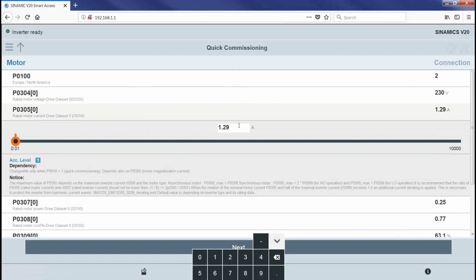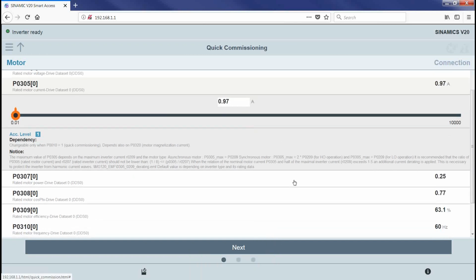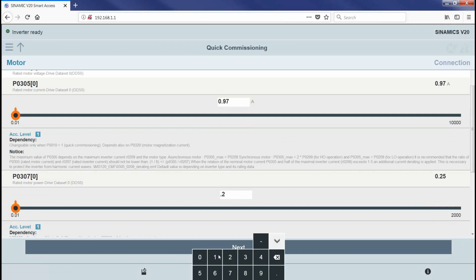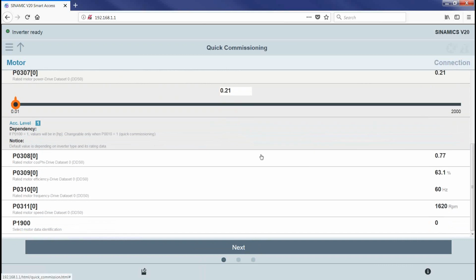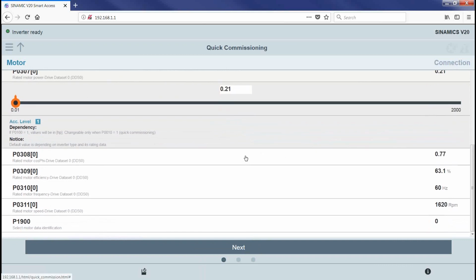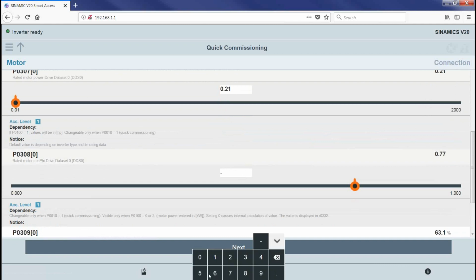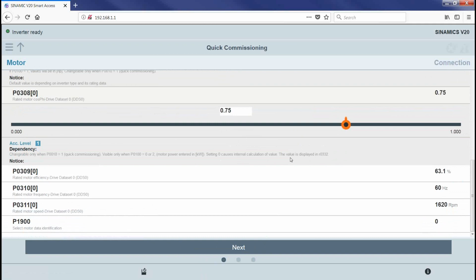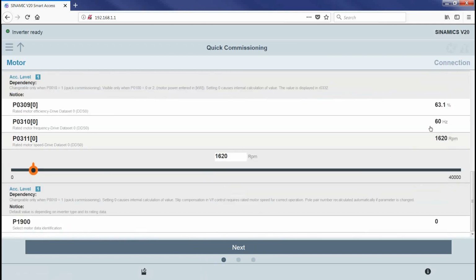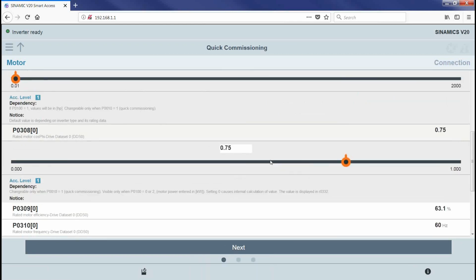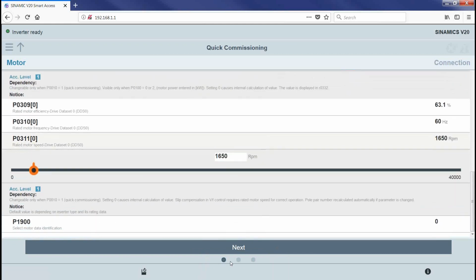Motor current. So here, if we click on the number, here's the pop-up again. If you're thinking about a tablet or a smartphone, it's going to pop up at the bottom. So I'm going to put 0.97, then arrow down to close that, because this is a 0.97 amp motor. It's a 0.21 kilowatt. So cosine phi on this motor is 0.77. I'm going to set it up for 60 hertz, and at 60 hertz, it's a 1650 RPM motor. So there's basically the information off the nameplate of the motor. Again, you got 3 dots, but next is going to take you to the next page.